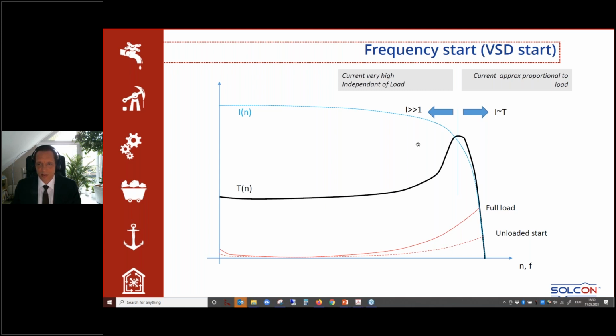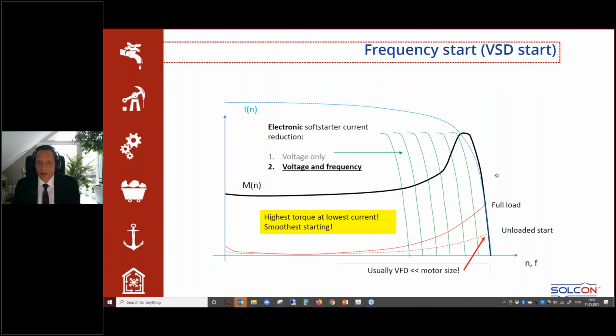So what does frequency starting do? In this case, you see you are reducing the frequency and you are shifting this stable point of the breakdown torque to the left. That means you are always on the higher side of the breakdown torque. And that means you have always a high torque at a low current. So this gives you a smoothest starting. The thing is, the VFD part of the IGBT starter is much smaller than the motor size because, as I said before, the load is very often starting unloaded, and that means the VFD portion is approximately similar in size to the load during starting and not the full size of the motor.